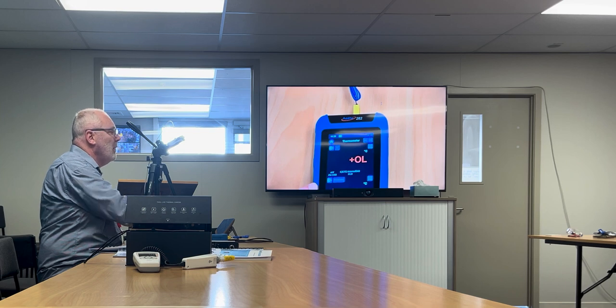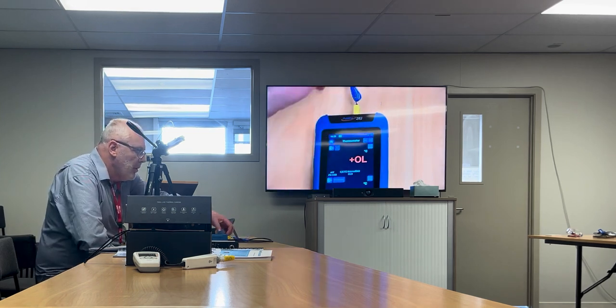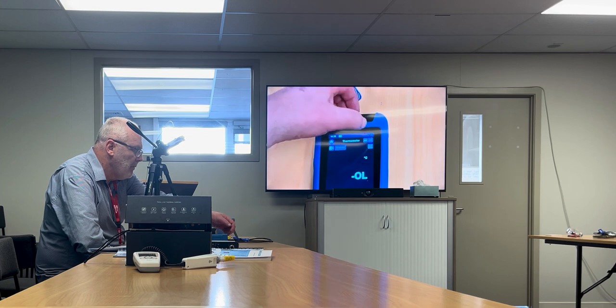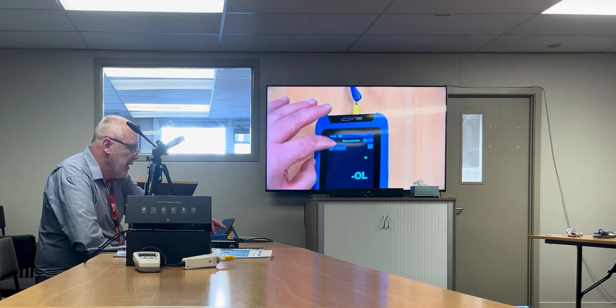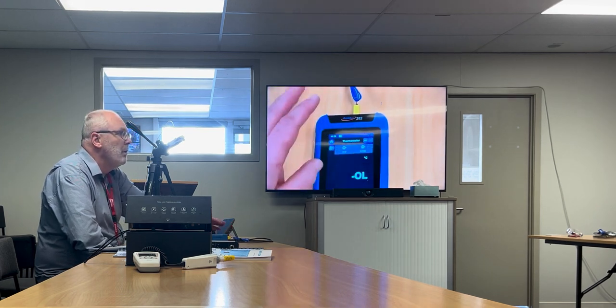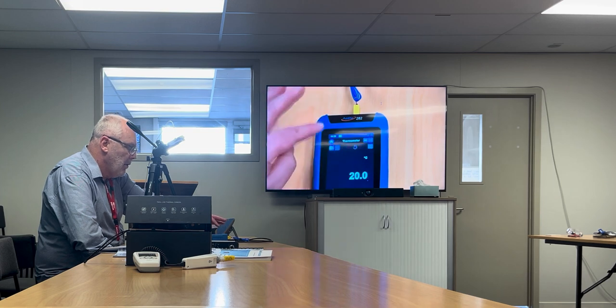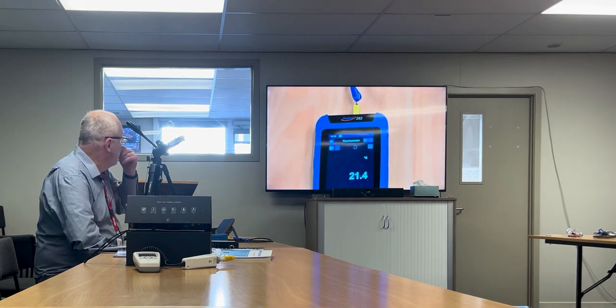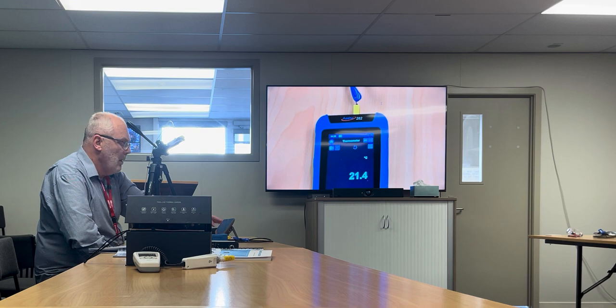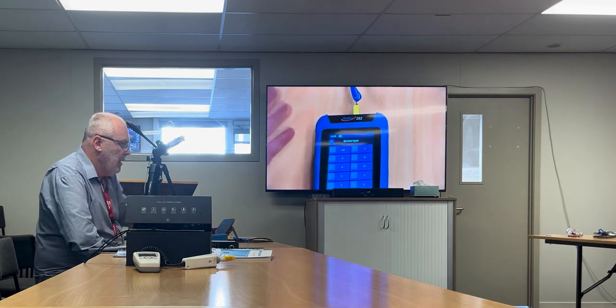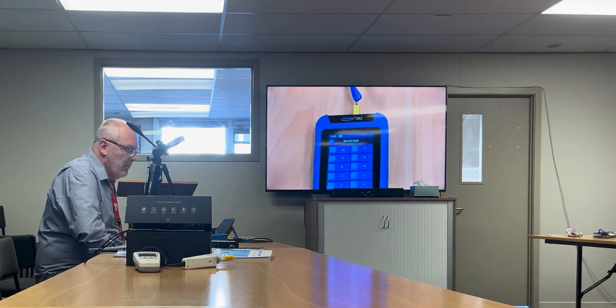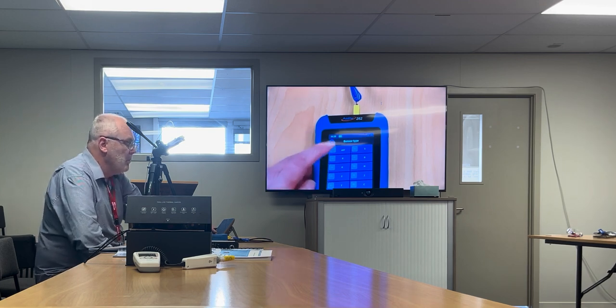So we'll turn off channel 1, for sake of argument, and on channel 2 we're going to change it - it's all touchscreen, as you've probably worked out - to a thermocouple. At the moment it's set to type K, but if I touch on the K, we can set it to any one of 50 million different thermocouples, including the bare millivolts, which is quite nice.